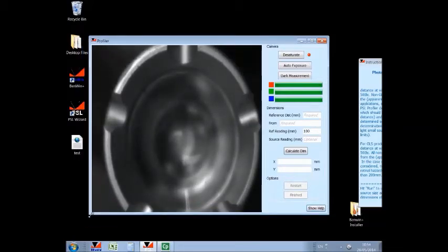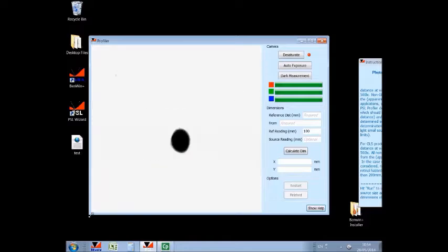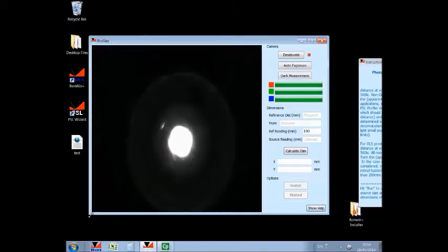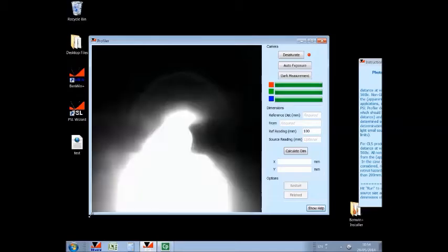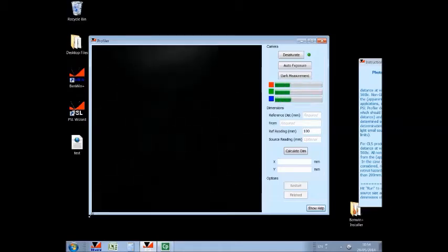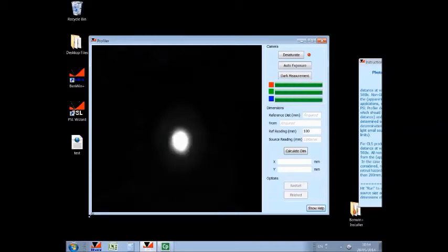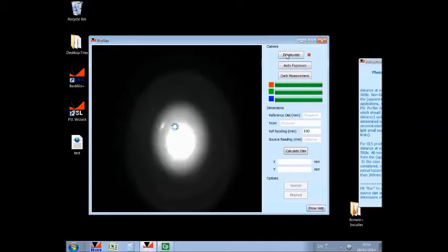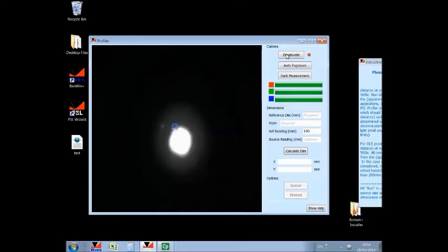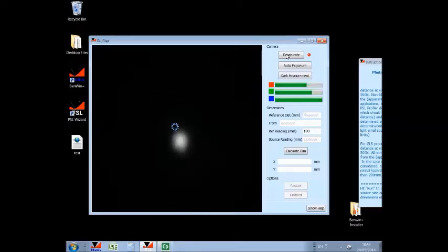calculation following this procedure. We can then power on the light source, and the first thing we have is saturation of the CMOS camera, and we can rectify that by turning the ND filter wheel downwards into increasing optical density. Perhaps we can go one step back and try to desaturate. Whether this will succeed or not, we will see. If the signal level is still too high, the software will prompt us.